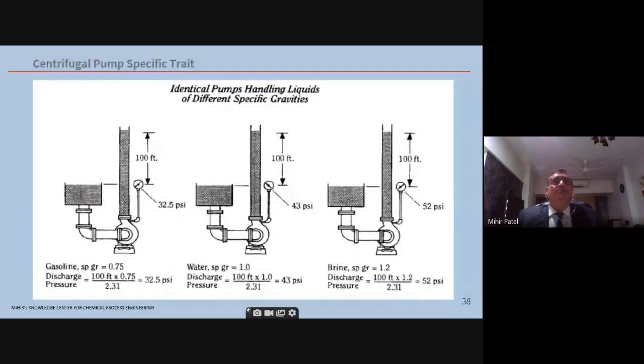Now, centrifugal pump. There is a very specific tendency of a centrifugal pump which many people may not be aware of. The impeller of a centrifugal pump, if it is designed for 100 feet, will build 100 feet irrespective of the fluid density. So if you have a fluid density of, let's say, gasoline 0.75, it will still give 100 feet. The discharge pressure in PSI will be very different. Water will give the same 100 feet. Brine of 1.2 will still give the same 100 feet. So what this means is that if you are designing an impeller, let's say a pump for gasoline service, when you retrofit that pump for a brine service, you have to be careful.